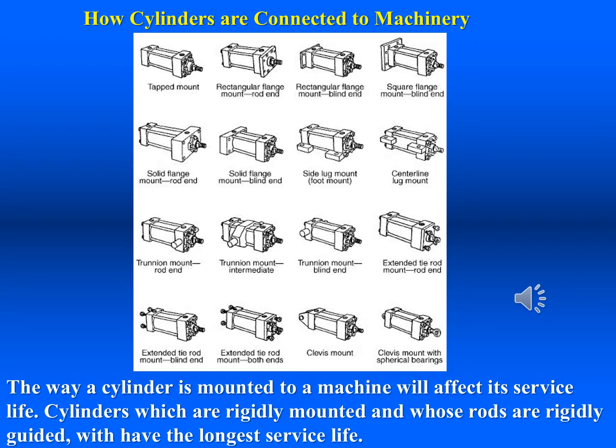The means by which a cylinder is mounted to the machinery determines its usable service life. When the cylinder is firmly bolted into place and its rod has mechanical guidance throughout its movement, the usable service life will be long. Often, though, cylinders are subjected to side loading, which places stressors on the rod gland and bushing. Other factors that decrease service life are exposure to the weather and dirty working environments.